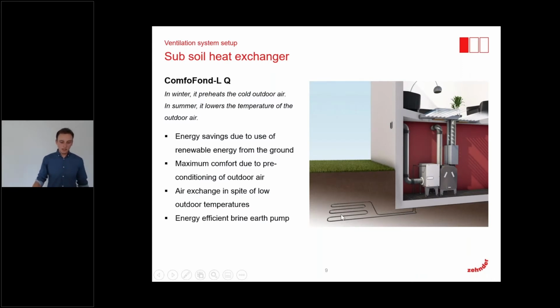Another accessory is our subsoil heat exchanger. The subsoil heat exchanger gains energy from the ground, where a collector lies at a depth of up to 2 meters. On the other side, we have the heat exchanger next to our unit, and a circulating brine brings the heat or the cold. In winter, when the outdoor temperature is low, we pre-temper the air and prevent the unit from freezing with the help of the subsoil heat exchanger. And in summer, it lowers the temperature of the outdoor air and provides a comfortable supply air temperature. And here we also have energy savings due to the use of renewable energies.